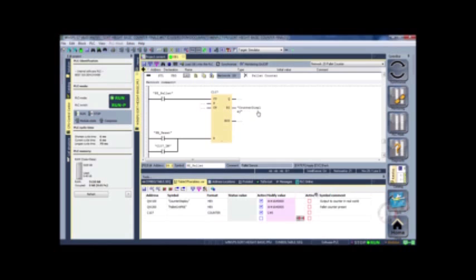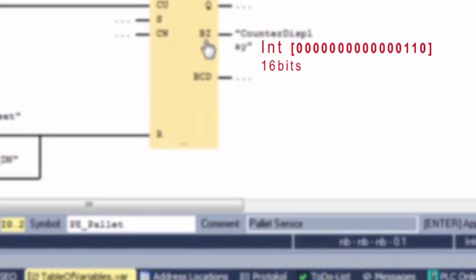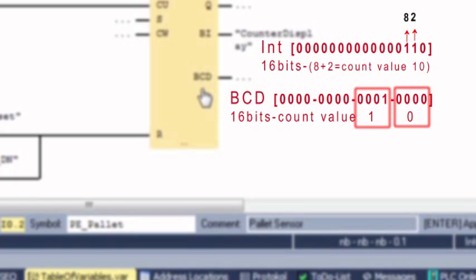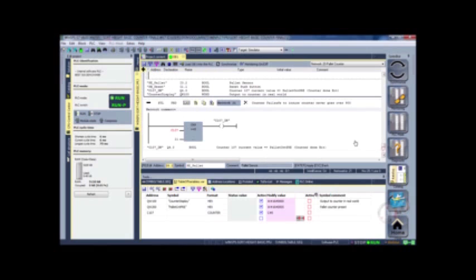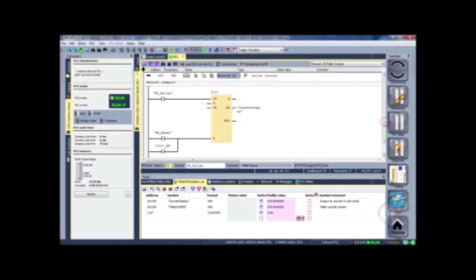So this counter resets itself after it reaches 11, which causes the counter display on the control panel to show 0 through 10. At 11, the counter gets reset to 0, so you never see the value 11 on the counter display. You'll notice there are two outputs for the current counter value: a binary one which is an integer, and a BCD (binary coded decimal). With BCD, we would have to create yet another rung to convert BCD to an integer, so we just use the counter's integer output since that is what the counter display requires.